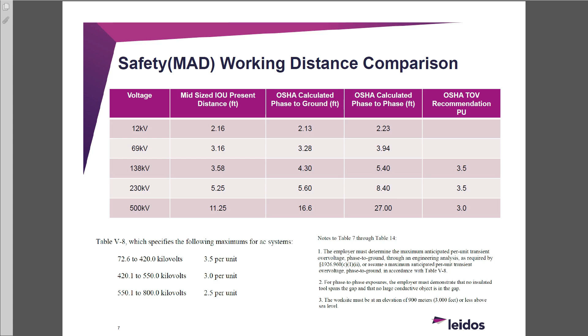So let's say you don't want to do a fancy study, and we're looking at 3.5, 3. If you go to the next slide, they give you this per unit table. As you can tell, the smaller you get, the closer you can get the phase-to-phase to phase-to-ground exposure. The one thing about phase-to-phase exposure is, generally on transmission and distribution, most utilities working on operating practices cover up the other two phases when they work, so we're only really worried about phase-to-ground most of the time.